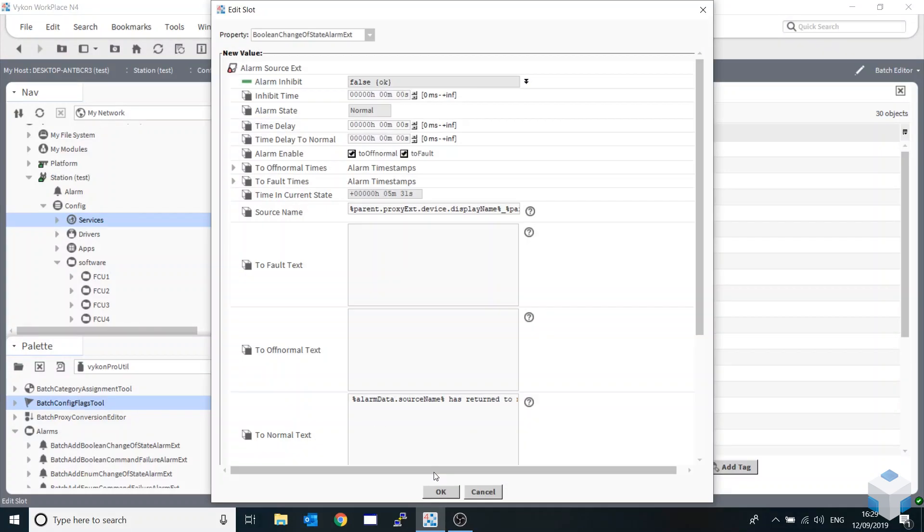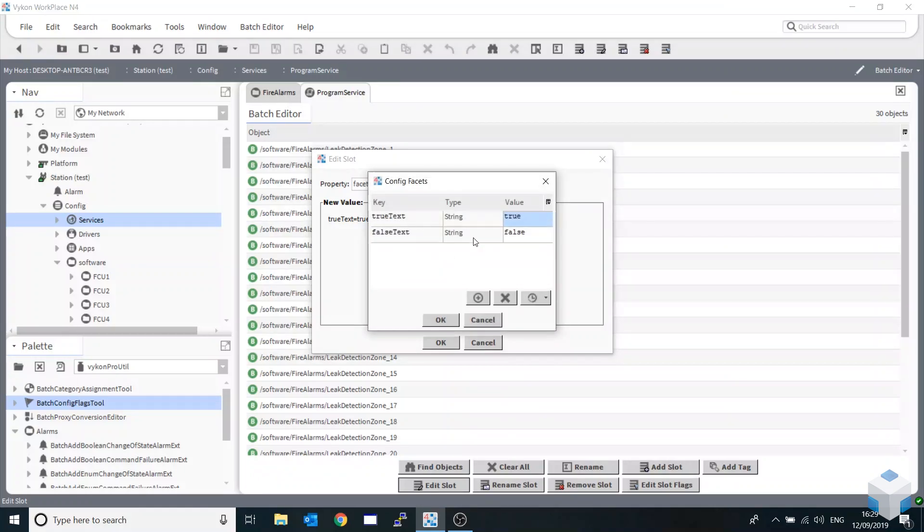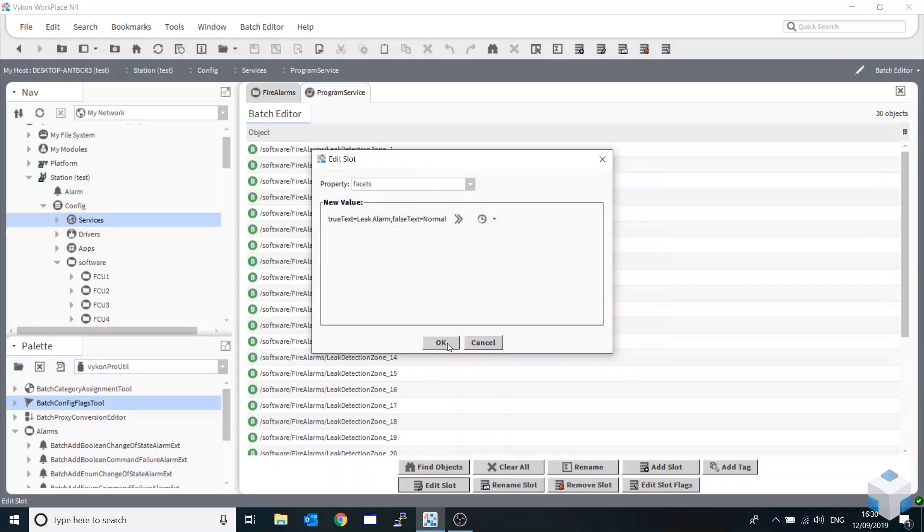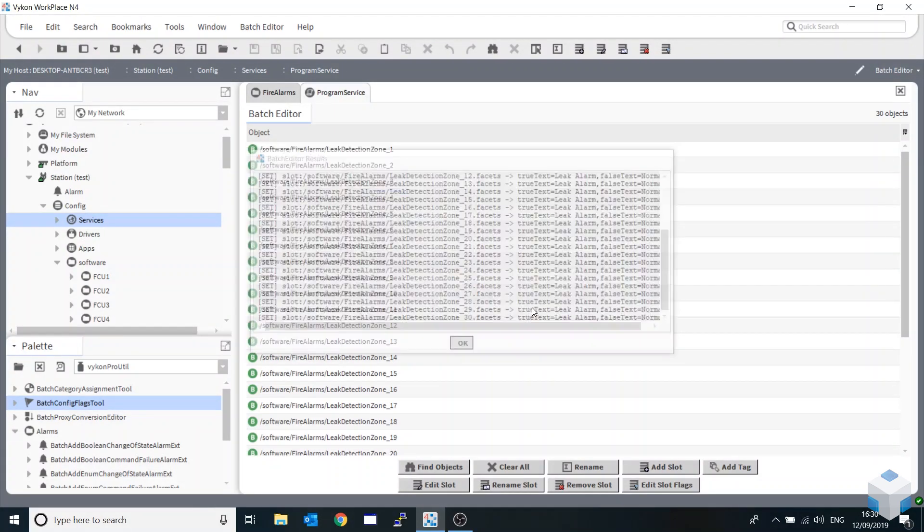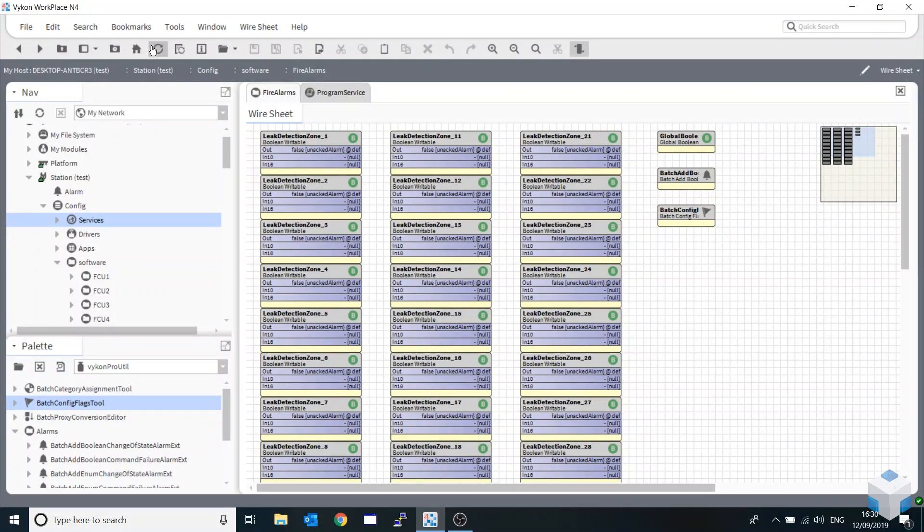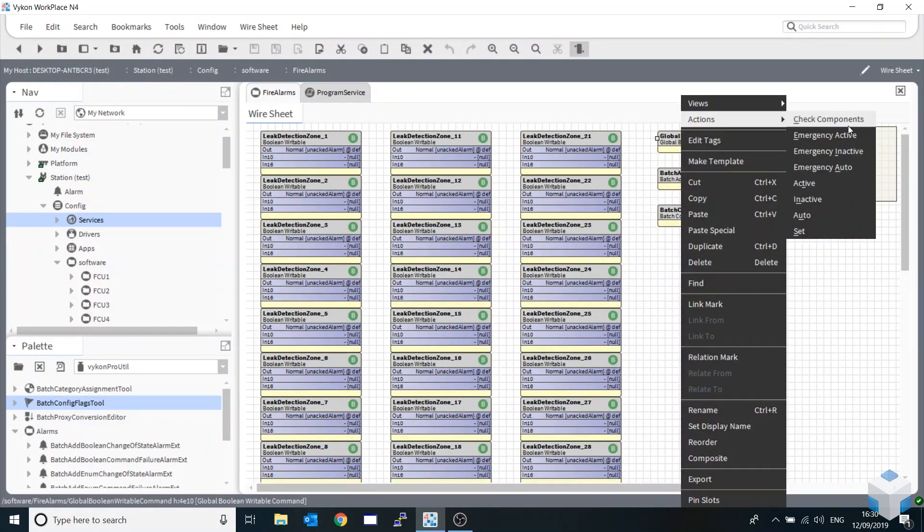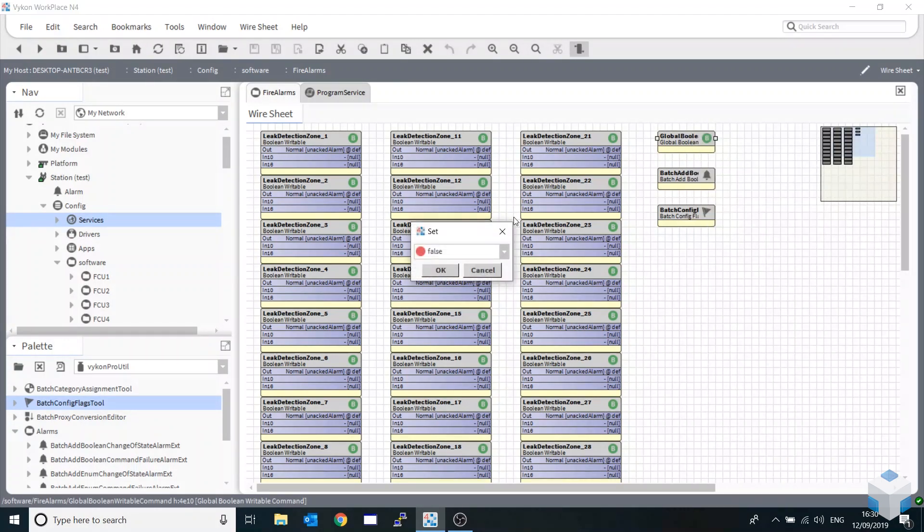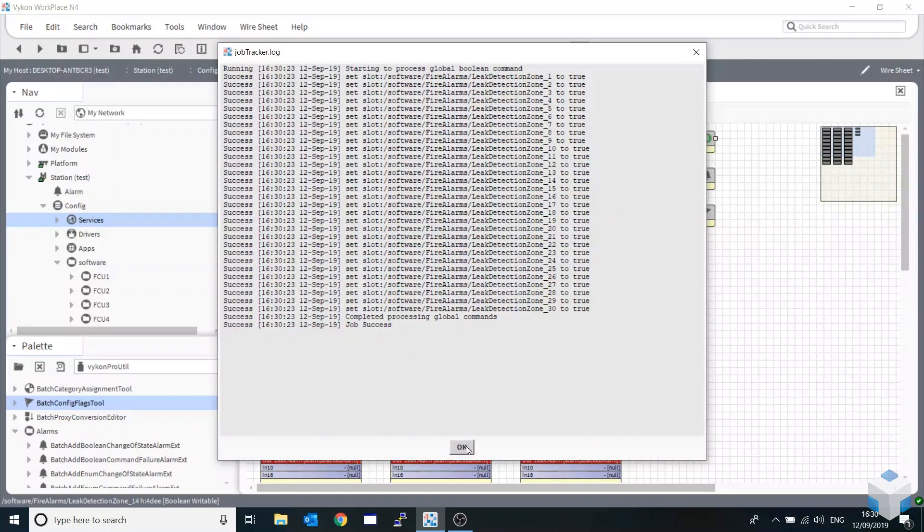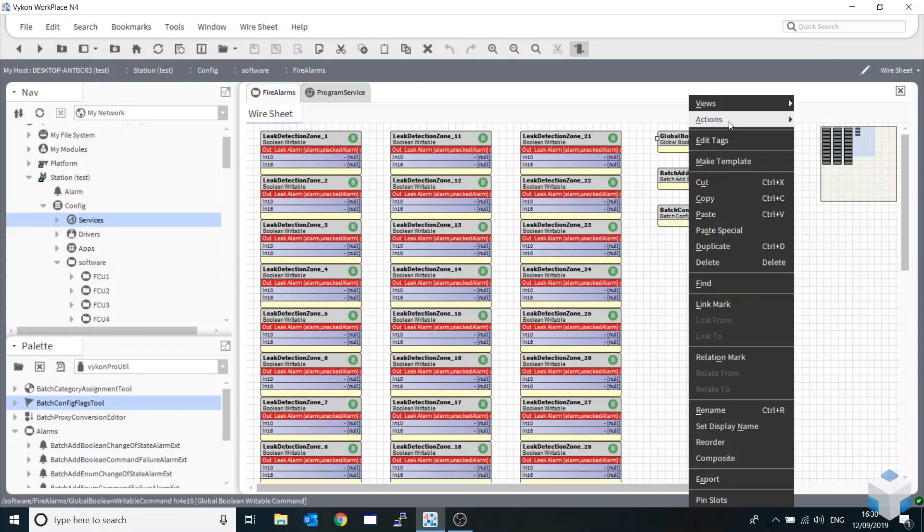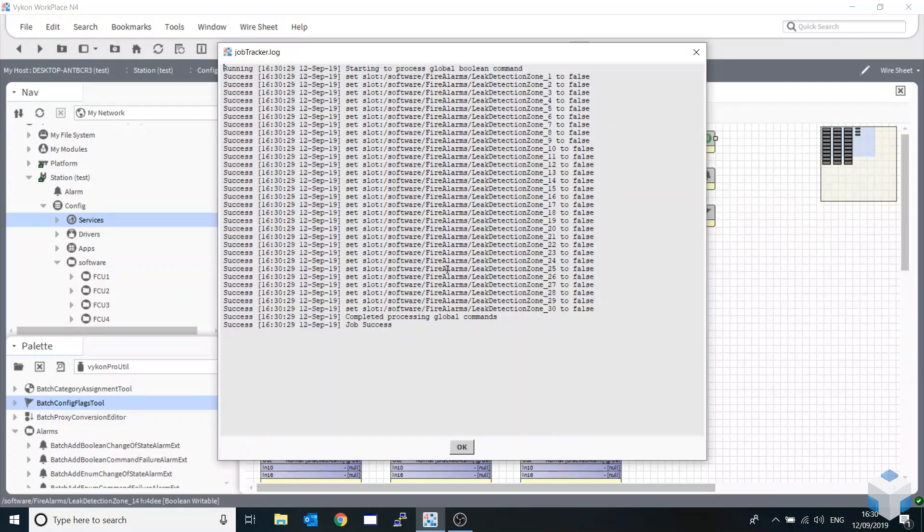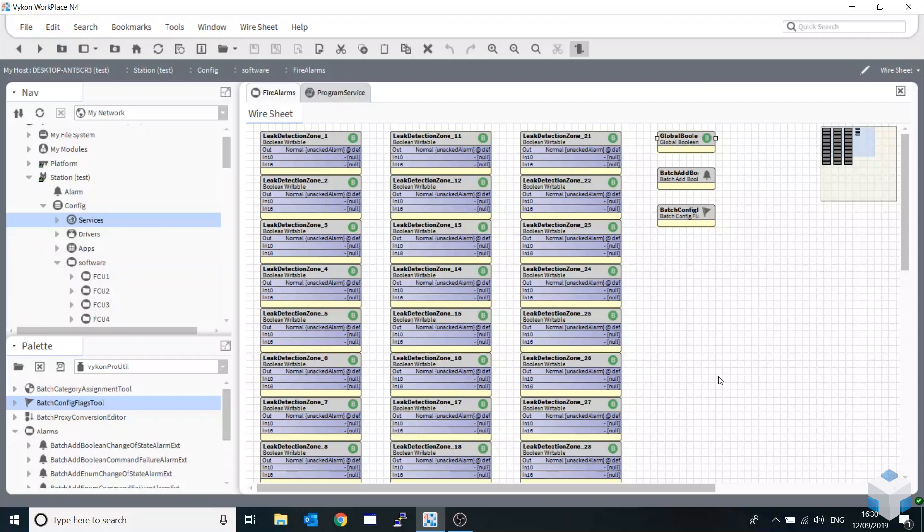I'm going to hit edit slot and I want to change just the facets. I'm going to say it's a leak alarm for our true state and normal. Hit that and OK. We have confirmation coming back that it's going to change the facets. Back over to fire alarm, I'm just going to reset that. As you can see it's now done the facets on all our points. Again by using a global command, set that true - leak alarm. And again actions set, make that false again.